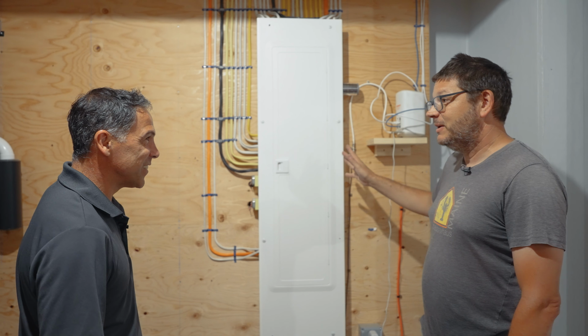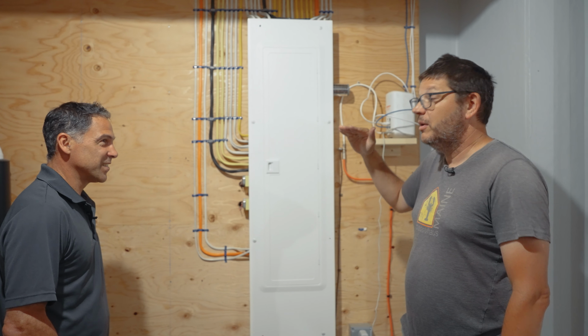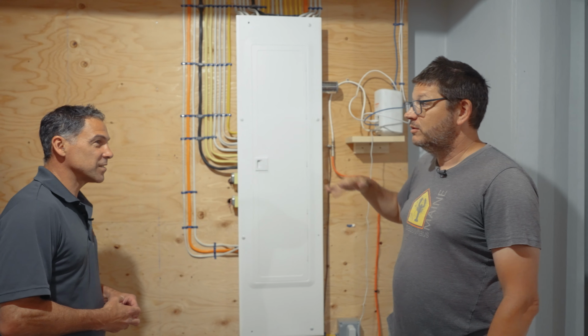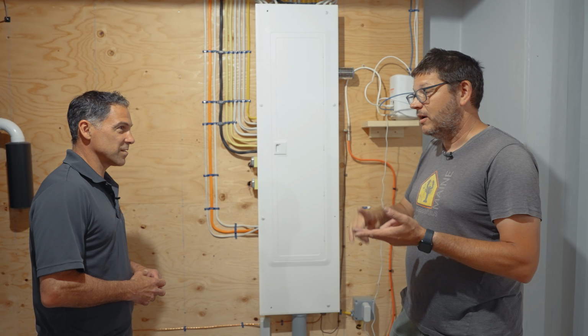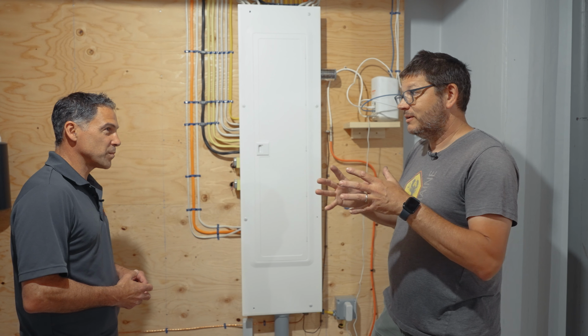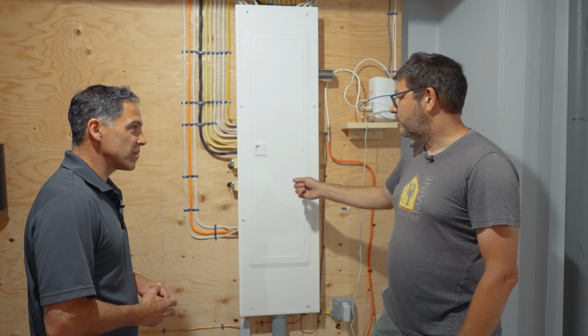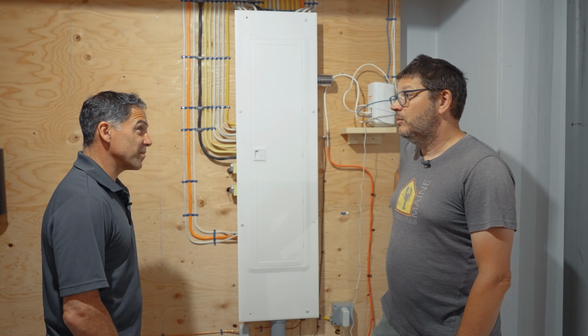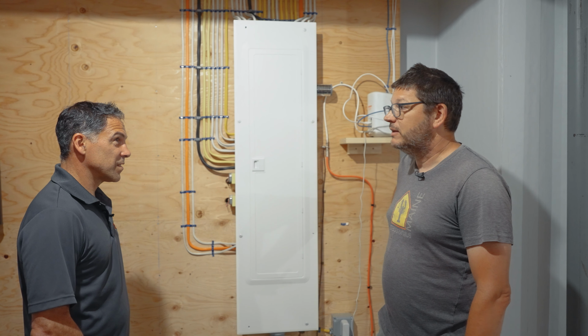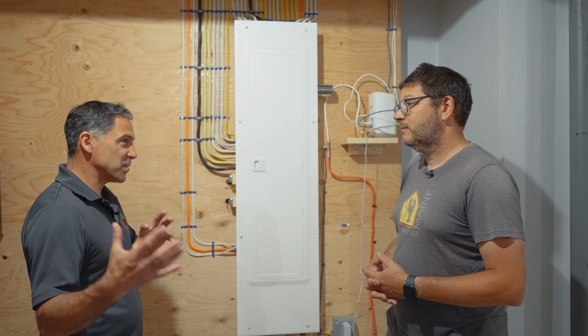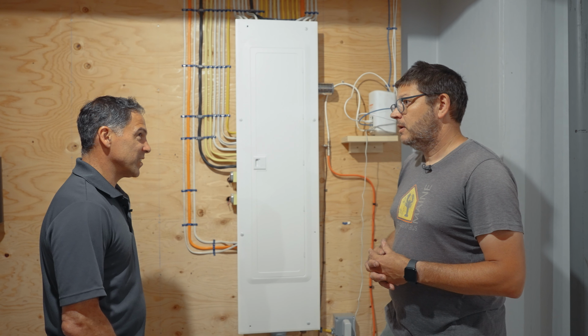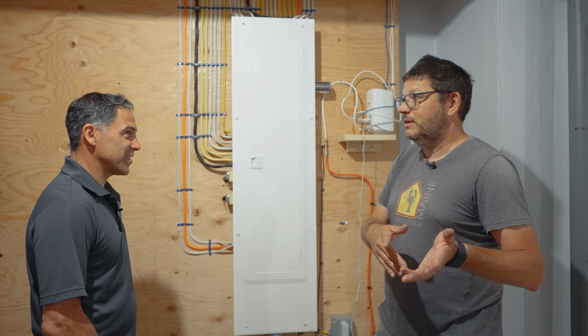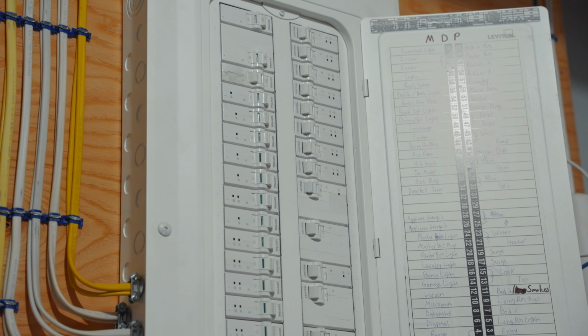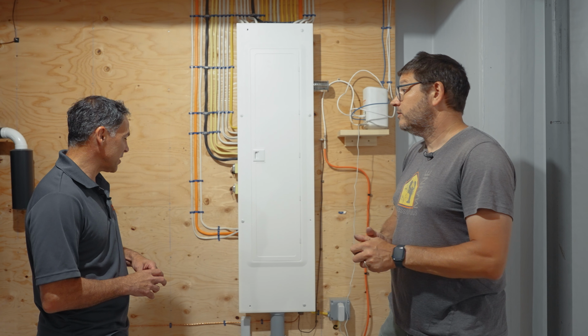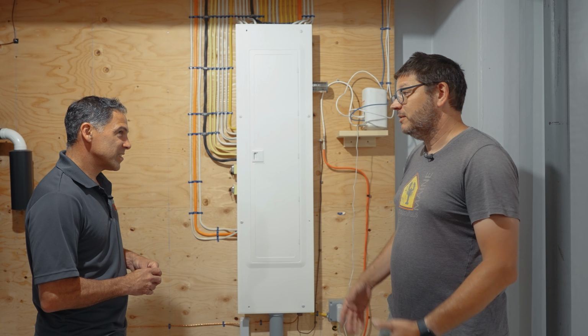One interesting thing about an all-electric house is that 200 amps is what we always put in. As soon as your heating system and hot water are electric, if you don't design the loads to be small, you could end up pushing up to a 400 amp service, which for an average house right out of the gate is another $15,000 to $18,000. So that's another benefit of maximizing the system and equipment - that $15,000 is probably the additional installation cost. That's part of the design phase, figuring that stuff out ahead of time so you know what you're getting into. The last thing you want is to do the electrical work and then have someone think they're going to plug in two cars - and no, you're not.